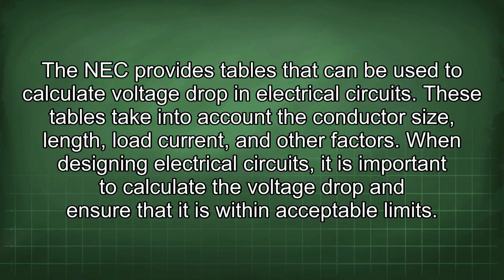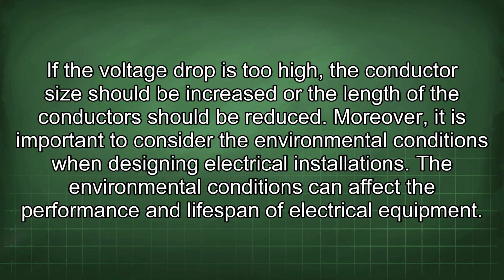The NEC provides tables that can be used to calculate voltage drop in electrical circuits. These tables take into account the conductor size, length, load current, and other factors. When designing electrical circuits, it is important to calculate the voltage drop and ensure that it is within acceptable limits.